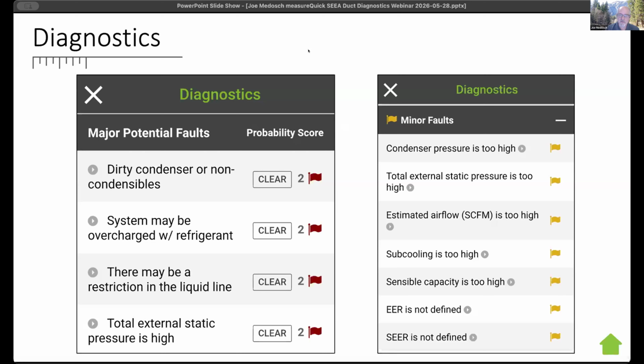And if you think it's an outside issue with refrigerant charge, you need to go measure airflow before you make any adjustments with refrigerant charge. It's a real common problem in our industry that people are like, oh, I think it's low on charge. Oh, you need to pull some charge out. You need to find out if the airflow is correct. And the airflow doesn't happen visually. You must use a tool to measure airflow.